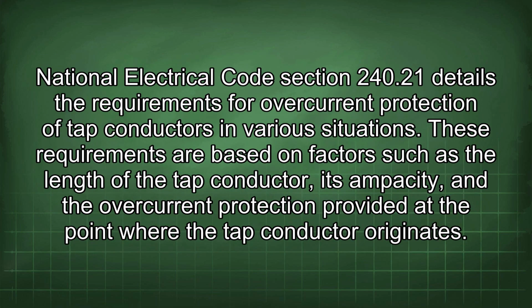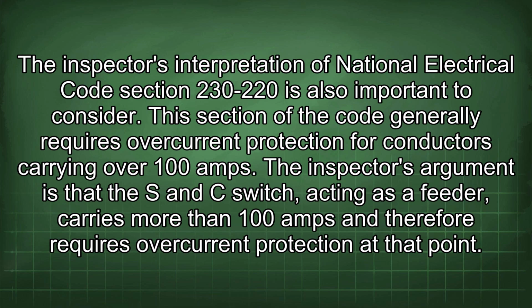National Electrical Code Section 240.21 details the requirements for overcurrent protection of tap conductors in various situations. These requirements are based on factors such as the length of the tap conductor, its ampacity, and the overcurrent protection provided at the point where the tap conductor originates. The inspector's interpretation of National Electrical Code Section 230-220 is also important to consider. This section of the code generally requires overcurrent protection for conductors carrying over 100 amps. The inspector's argument is that the S and C switch, acting as a feeder, carries more than 100 amps and therefore requires overcurrent protection at that point.